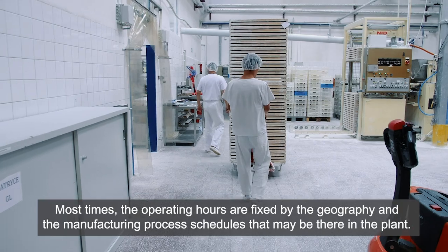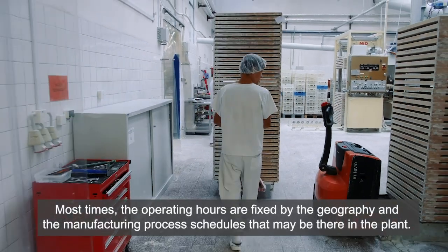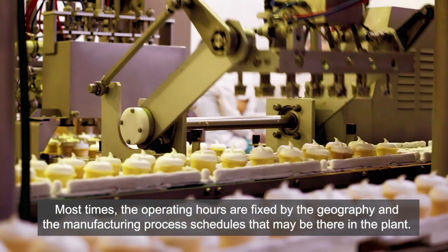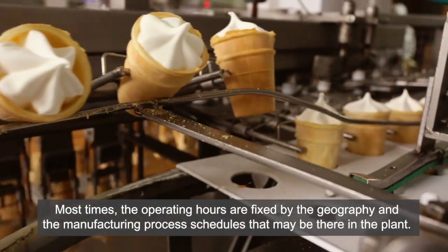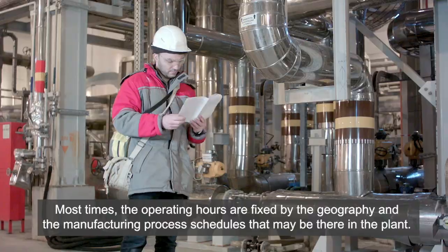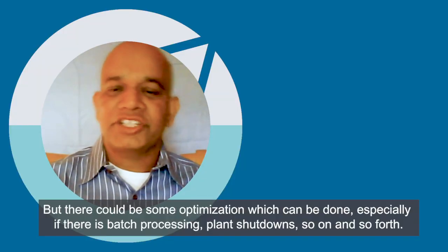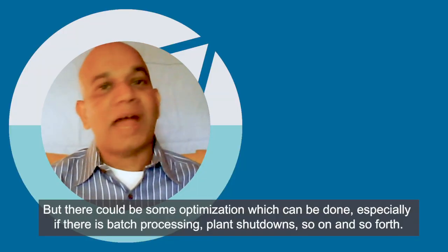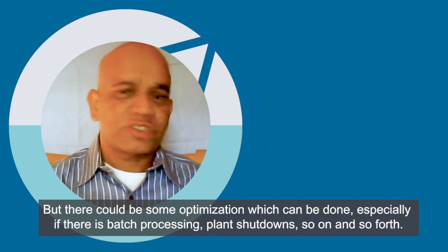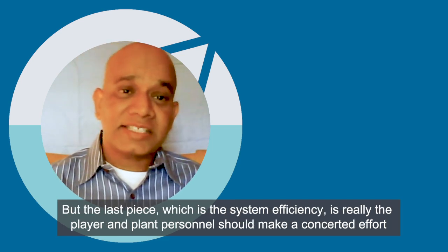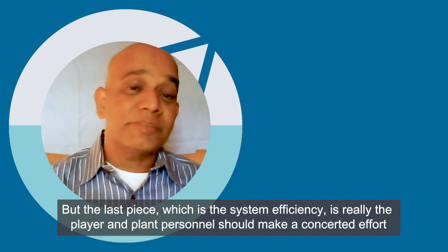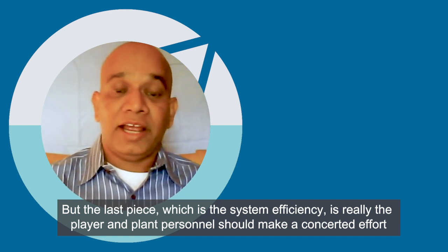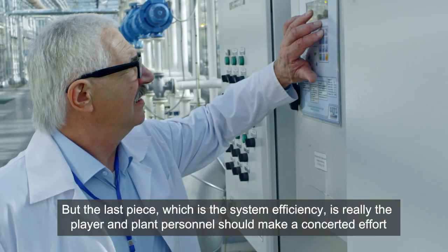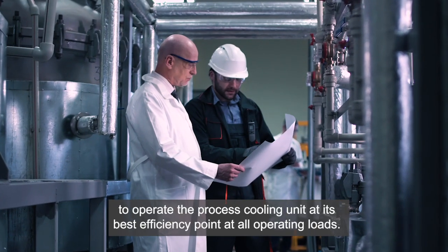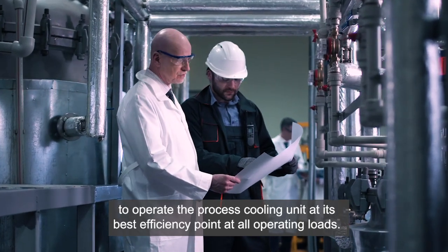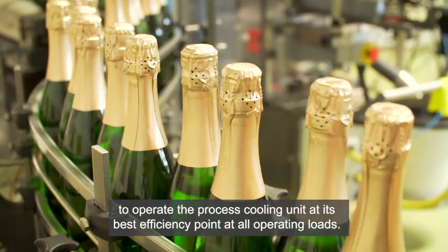Most times, the operating hours are fixed by the geography and the manufacturing process schedules that may be there in the plant, but there could be some optimization which can be done, especially if there is batch processing, plant shutdowns, and so forth. But the last piece, which is the system efficiency, is really the big player, and plant personnel should make a concerted effort to operate the process cooling unit at its best efficiency point at all operating loads.